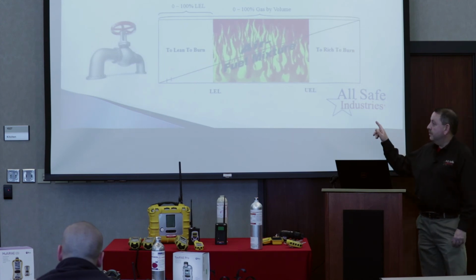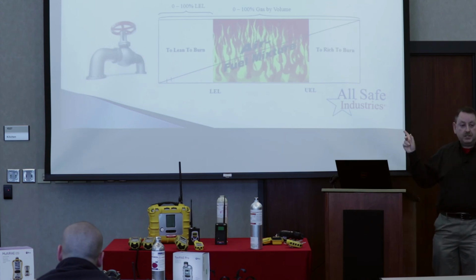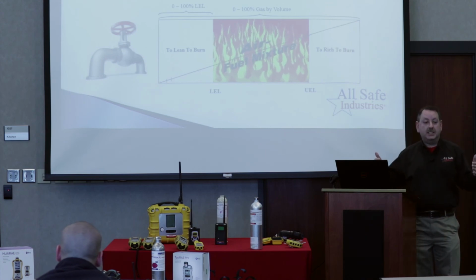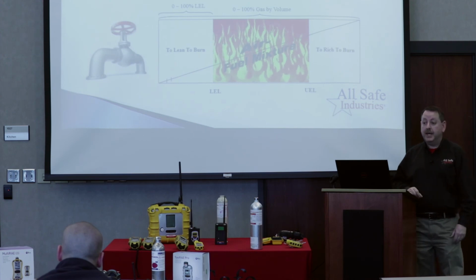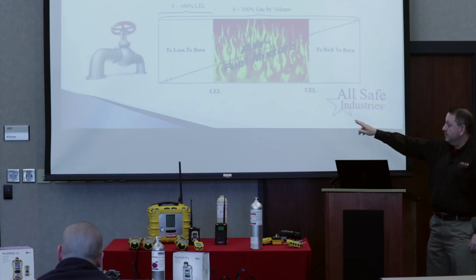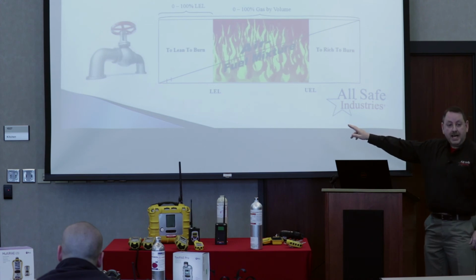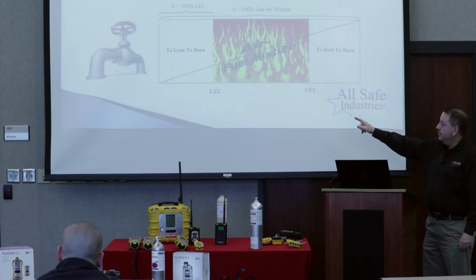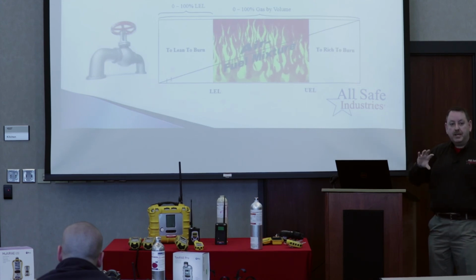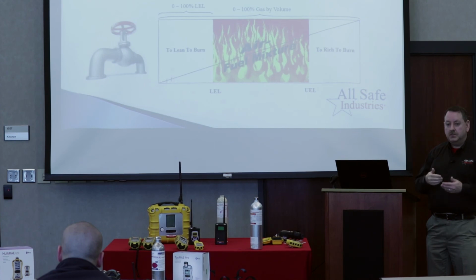So if you see the graph at the bottom of the page, and you see the picture of the gas valve, imagine that I could seal off this room, turn on that valve, and start to fill this room with flammable gas. So we'll start off in this bottom left-hand corner on that diagonal line, and as we start to fill the room with flammable gas, we're eventually going to reach that proper air-fuel mixture where all I need is a spark or an ignition source to set it off. That's considered the lower explosive limit.